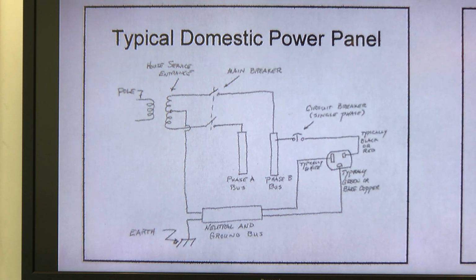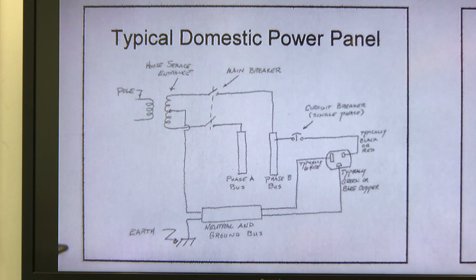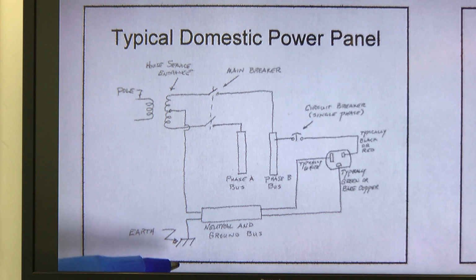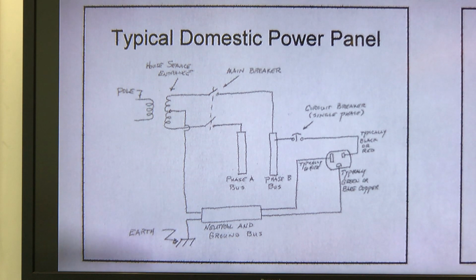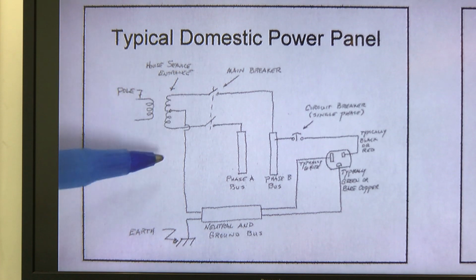And furthermore, when you go into your electrical panel, that neutral is a special copper bus. The bus bar itself is basically a long rectangular piece of copper, probably tin coated, that has tapped holes in it for screws and such. And that's where you make your electrical and ground connections. There's also a large conductor which is actually buried in the ground near the service panel. And that's what's called the earth connection. And that is really true. It really does go into the soil. So that's your service entrance.